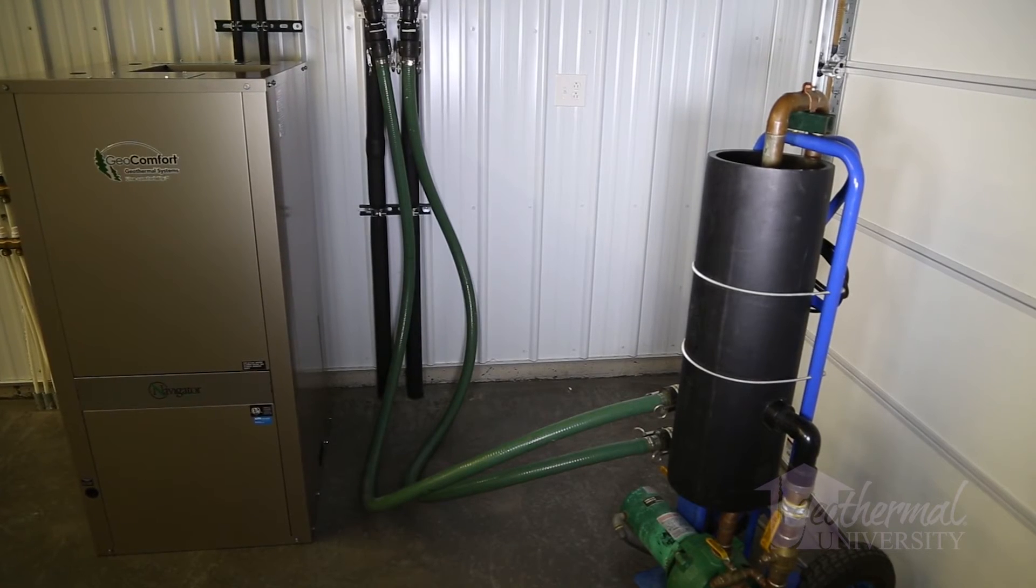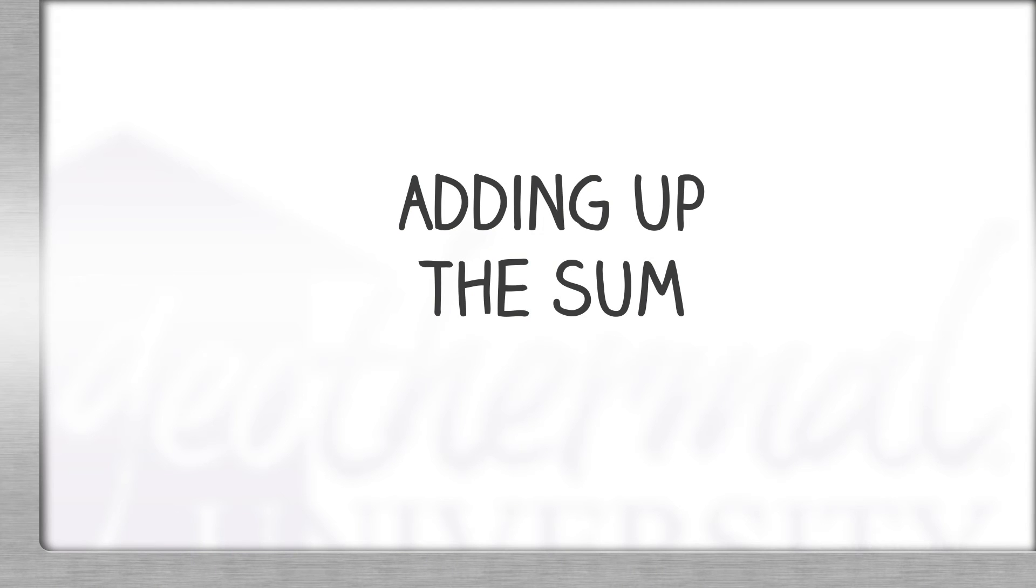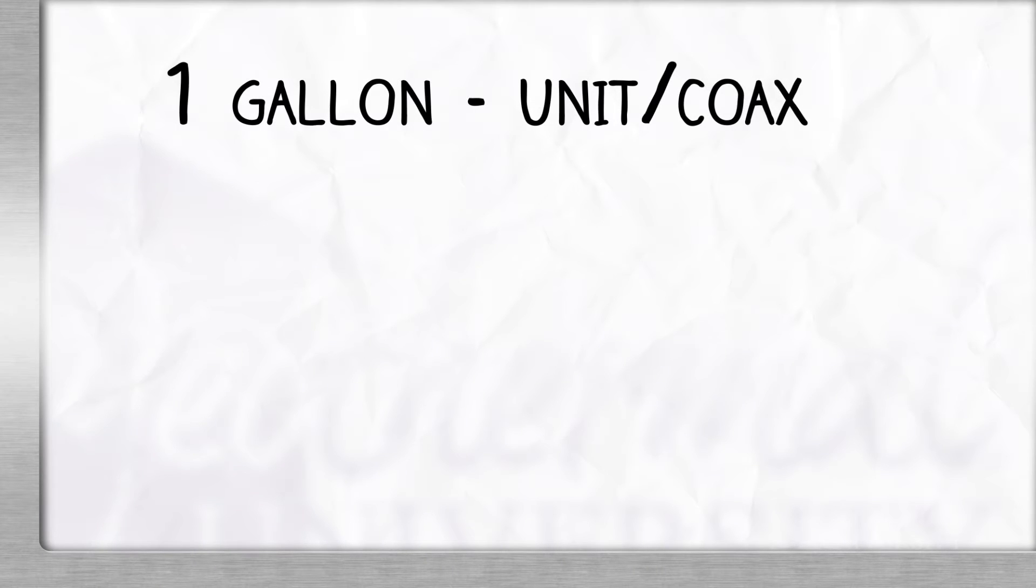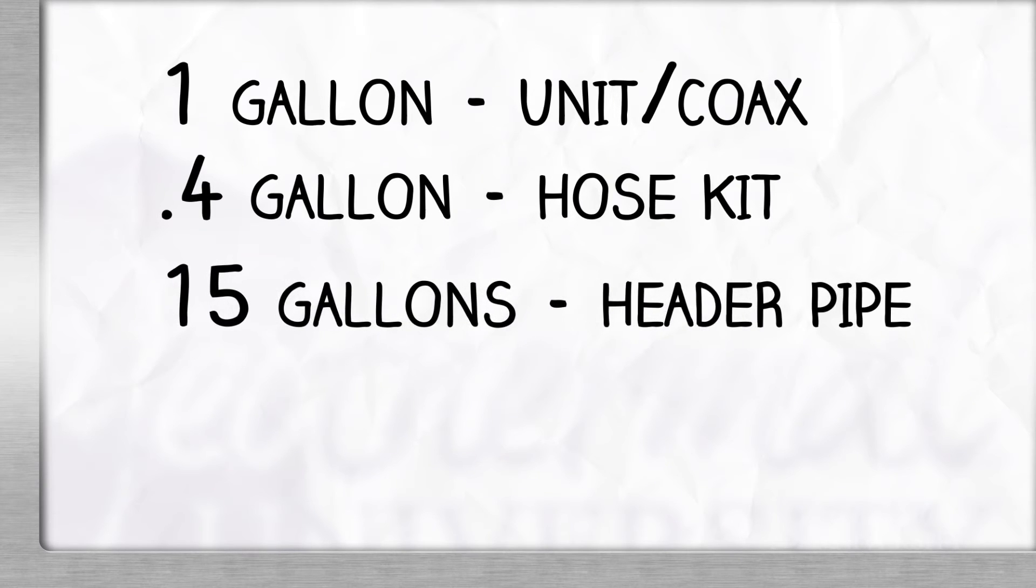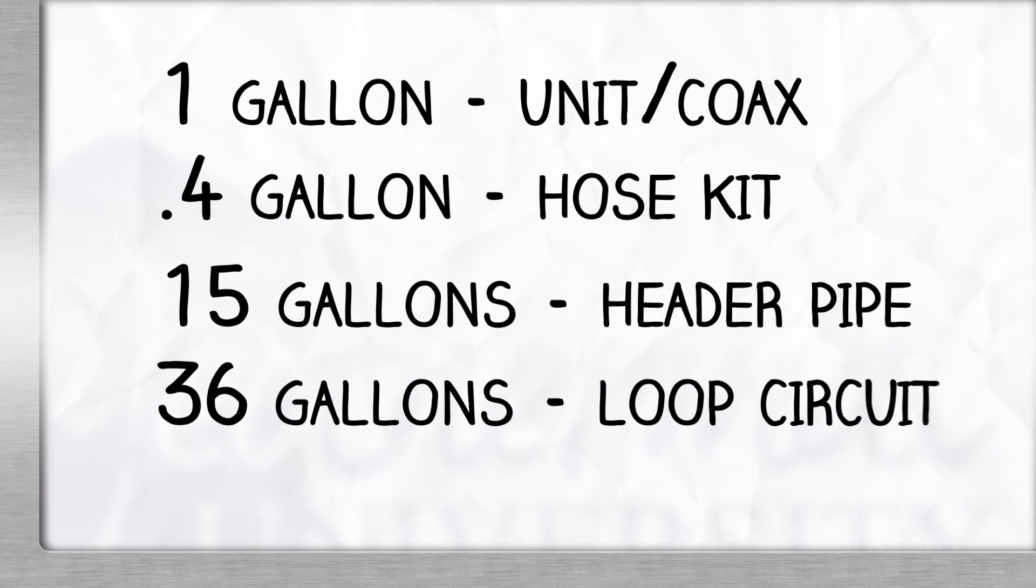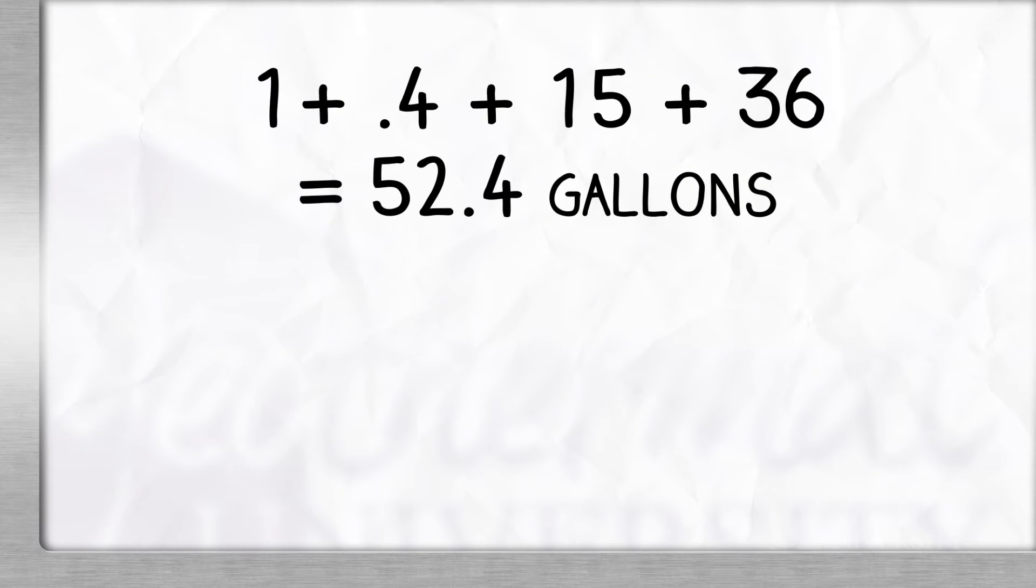Now that we have performed all the gallon to component calculations, we simply need to add up the sum. First, we have one gallon in the unit and coax. Second, we have 4 tenths of a gallon in the hose kit. Then we have 15 gallons in the header pipe. And last, we have 36 gallons in the loop circuits. So, our total is 1 plus 4 tenths plus 15 plus 36 equals 52.4 gallons.